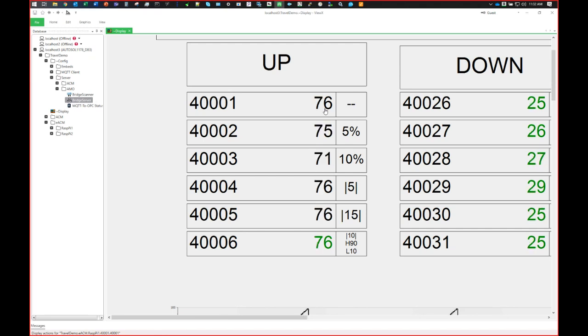There we go. So what'll happen when 40,006 is triggered again? 2 things. First, the entire device will change its publisher from 10 seconds down to 1 second. So you see, I'm getting a much higher resolution picture of my entire device right now because 40,006 is triggered. And it happened again on the lower trigger. And 40,006 itself doesn't have its deadband active. So this is designed to give you the ability to give your operators higher resolution data during specific alarm events.